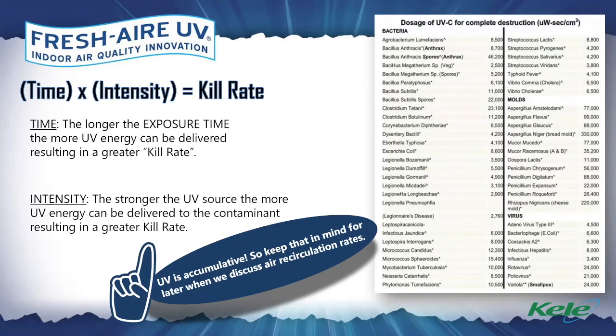And as you see here, this is a small cross-reference of different microorganisms that require a certain amount of dosage for inactivation. This is one of the reasons why healthcare, the engineering community, the scientific community has really embraced UVC light as a de facto means to disinfect, because it's a mathematical certainty that if we deliver the lethal dosage, we can achieve any inactivation rate. And the same cannot be said for other technologies out there in the marketplace.